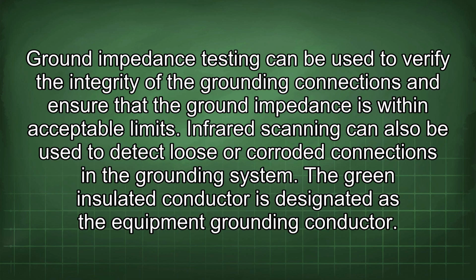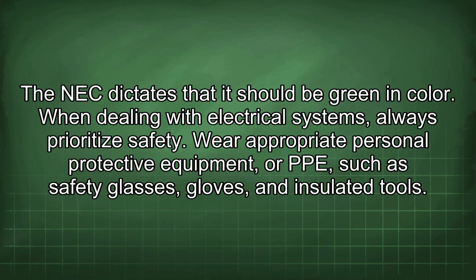Regular inspection and testing of the grounding system is important to ensure that it is functioning properly. Ground impedance testing can be used to verify the integrity of the grounding connections and ensure that the ground impedance is within acceptable limits. Infrared scanning can also be used to detect loose or corroded connections in the grounding system. The green insulated conductor is designated as the equipment grounding conductor. The NEC dictates that it should be green in color.